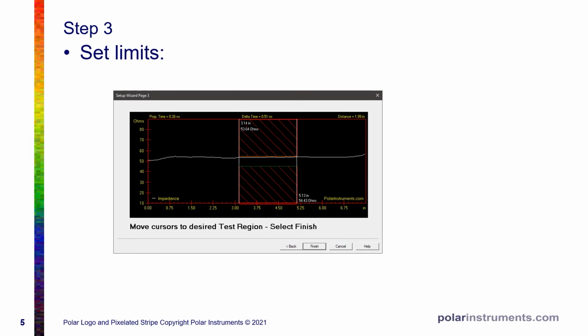In step 1 and step 2, the CITS determined the length of the probe and the length of the trace. Now in step 3, the measured trace is shown on screen in the dialog in front of you, and you can take the cursors and move them left or right, and you can use those to set the test limits that you will use in the actual test. So you either set those from the 50 to 80% of the trace, or the most flat region in the trace, or the area of the trace that's been specified by your customer. Click Finish and your test will be set up and complete.